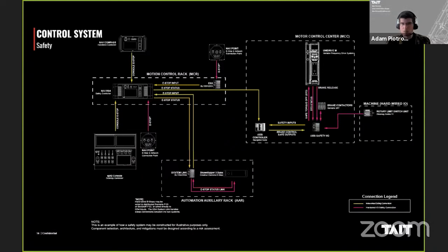Similar components, but we've shown a little extra here since we want our limit stack on our machine. That's brought in via hard IO to some IO modules, which talk via the field bus to the PLC in the MCC, linked back to the safety master. This could be limit switches on the machine, or in the case of the nav point, hard IO of the e-stop button itself brought into the IO located in the MCR and forwarded to the safety master.